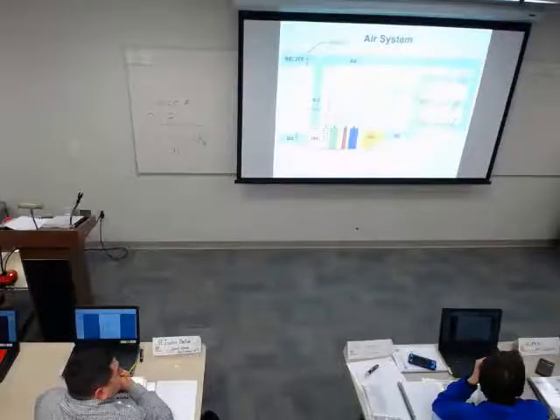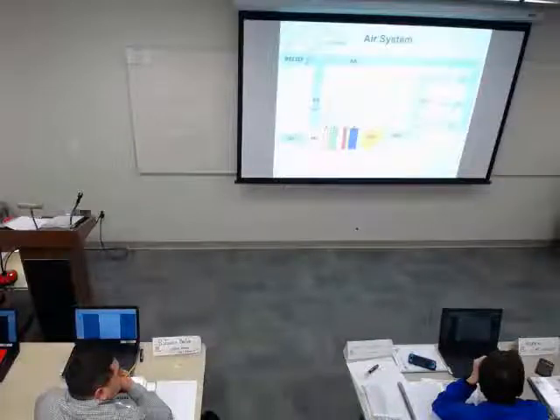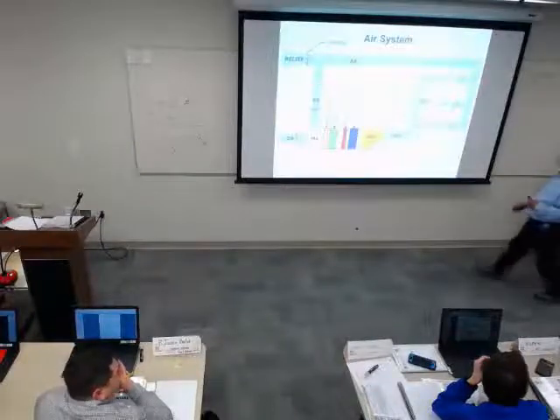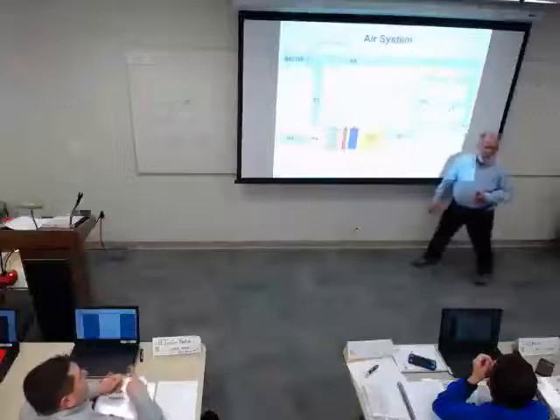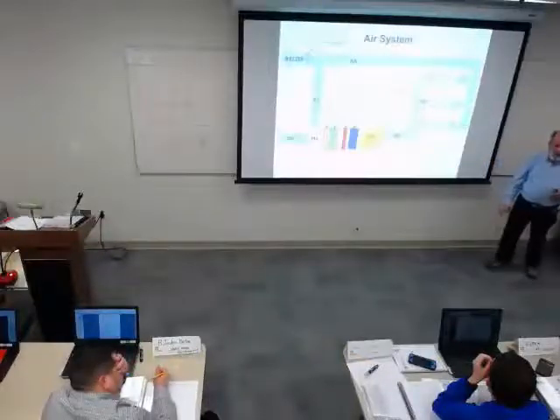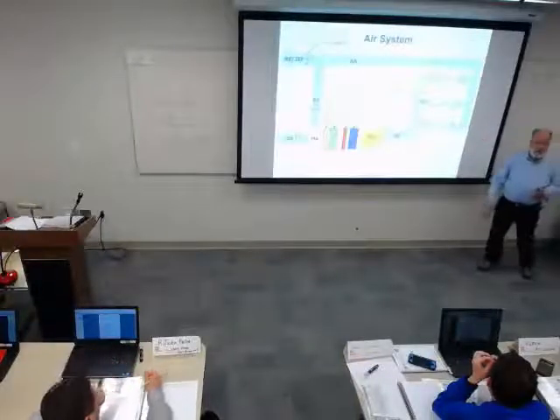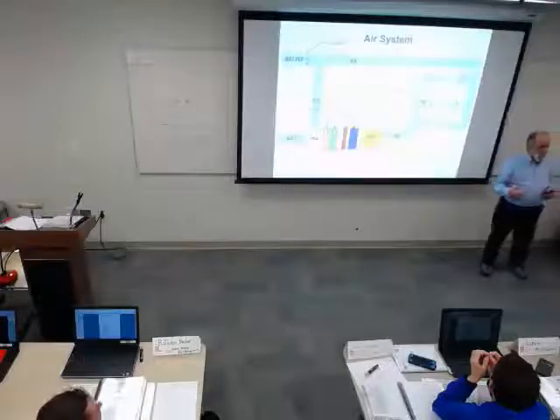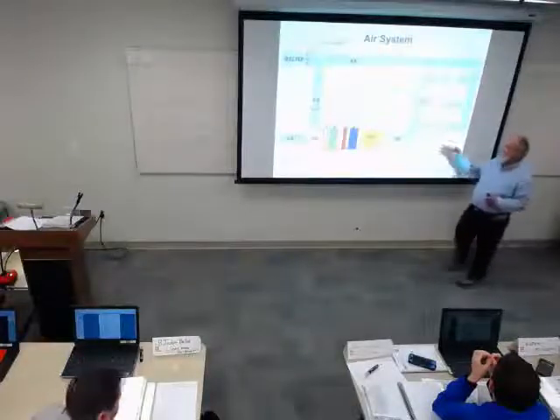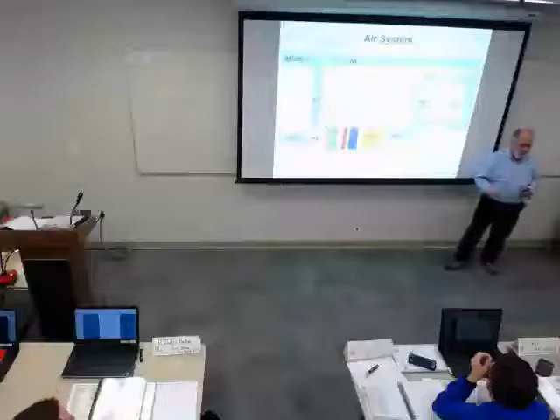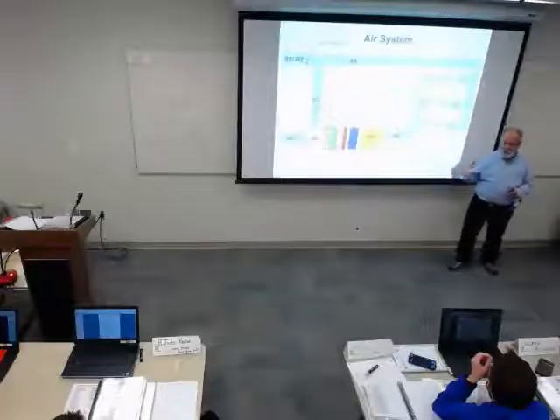And we're talking more about details here, but as the air comes in, this is the supply side, and it will control how much air goes out on this side. In essence, it's setting right here, like an automatic damper, and it'll change the airflow through the space. As the space requires more cooling, it opens up wider. As the space requires less cooling, it closes. That's how the VAV works.